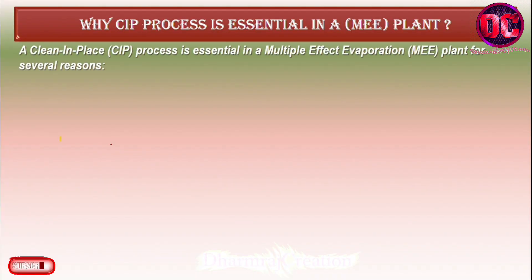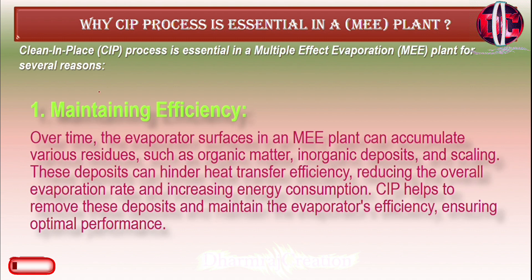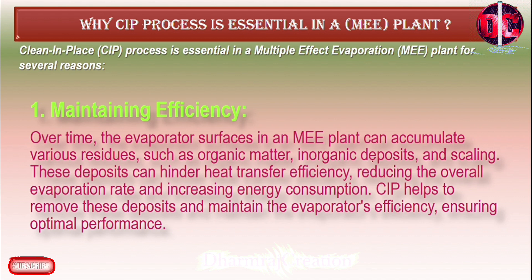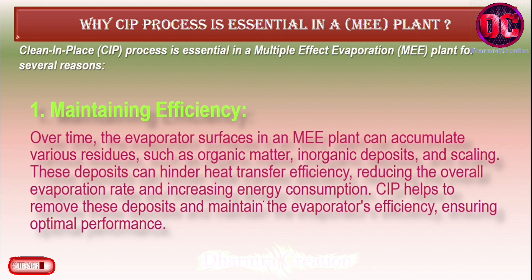A clean-in-place (CIP) process is essential in a multiple effect evaporation (MEE) plant for several reasons. First, maintaining efficiency over time: the evaporator surfaces in an MEE plant can accumulate various residues such as organic matter, inorganic deposits, and scaling. These deposits can hinder heat transfer efficiency, reducing the overall evaporation rate and increasing energy consumption. CIP helps to remove these deposits and maintain the evaporator's efficiency, ensuring optimal performance.